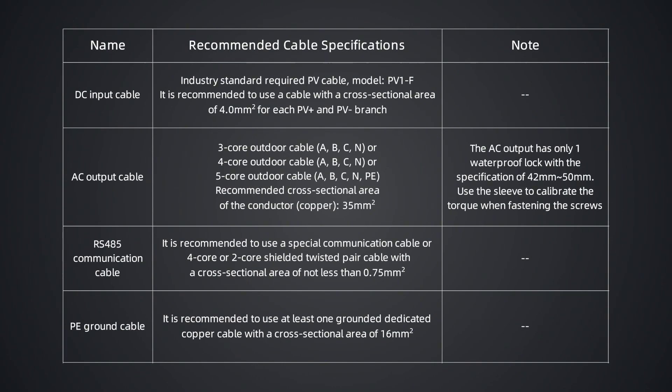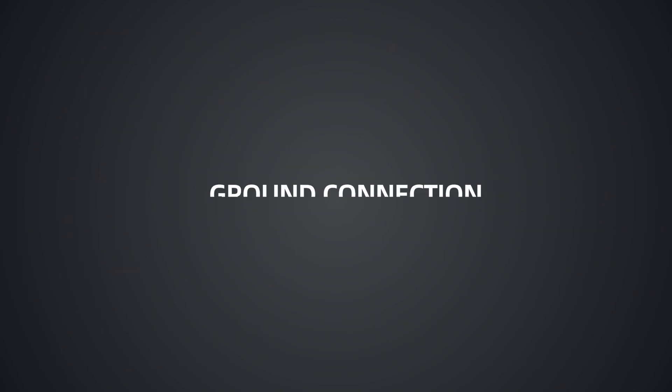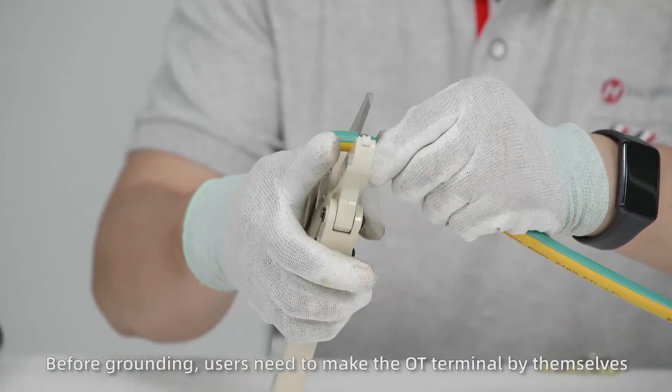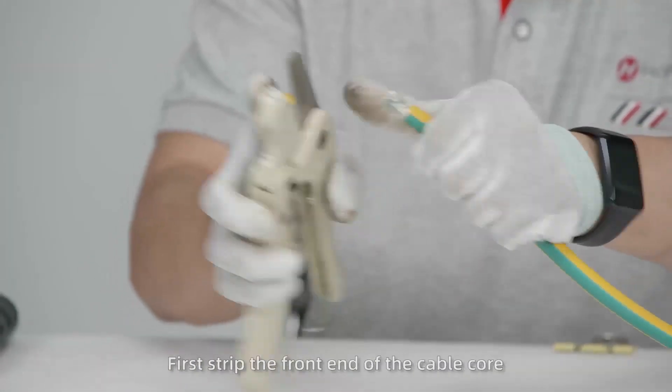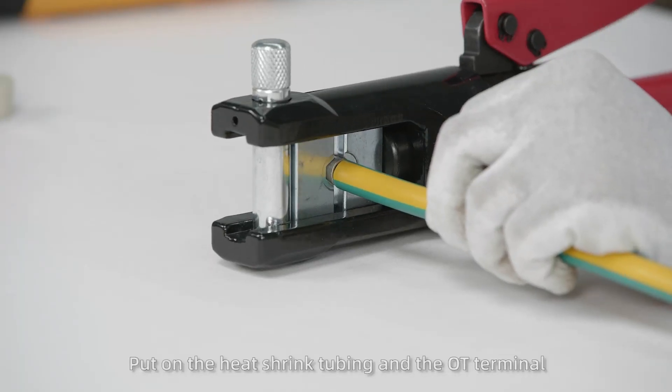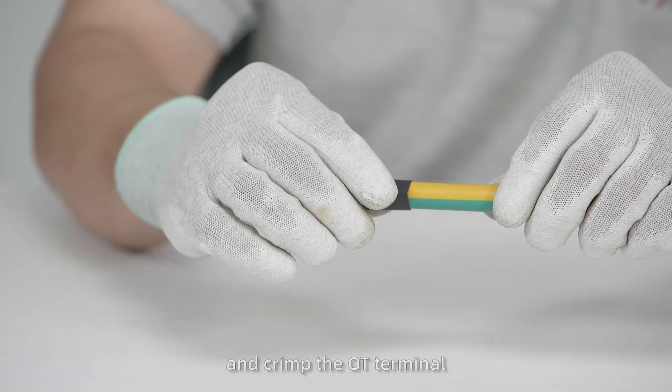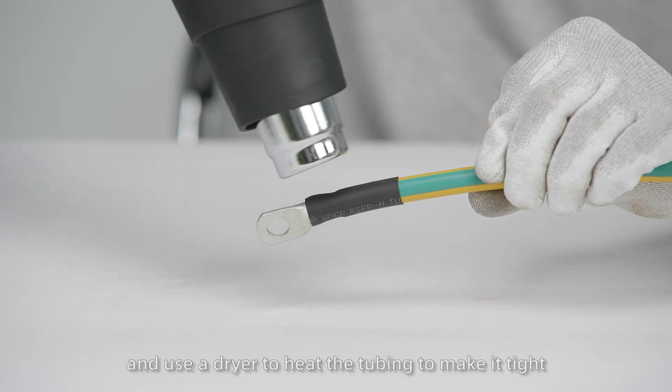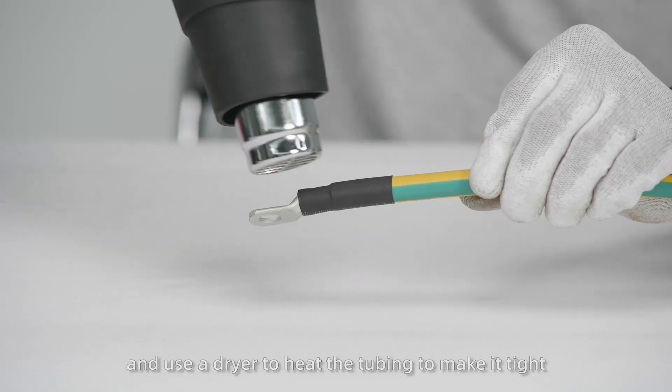Step 2. Cable Connection. First, connect the ground cable. Before grounding, users need to make the OT terminal by themselves. First strip the front end of the cable core, put on the heat shrink tubing and the OT terminal, and crimp the OT terminal. Then move the heat shrink tubing forward to cover the seam and use a dryer to heat the tubing to make it tight.